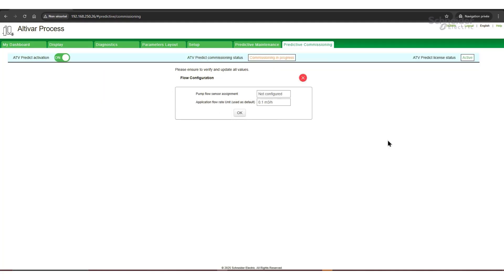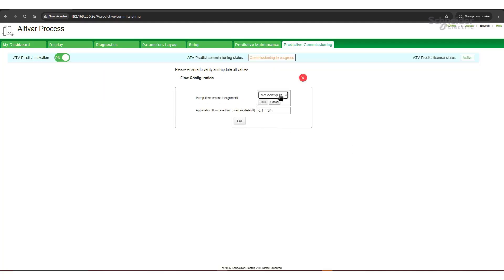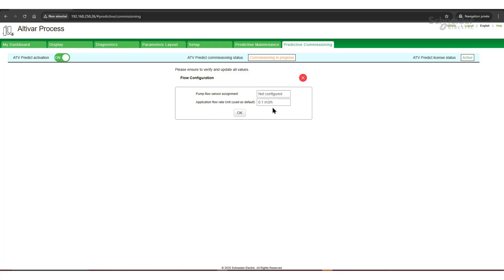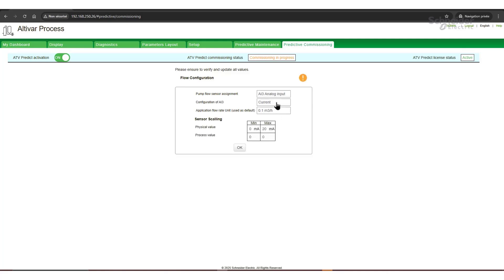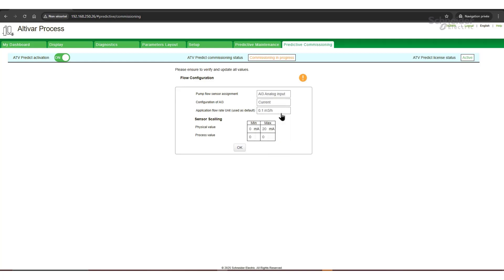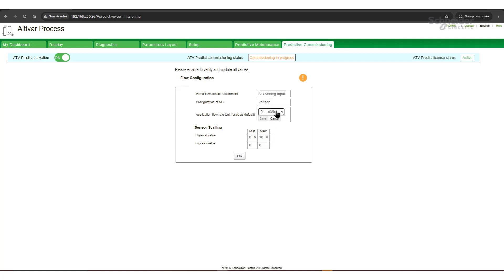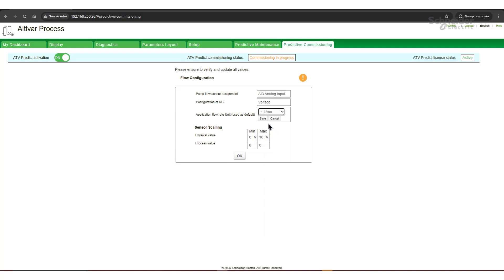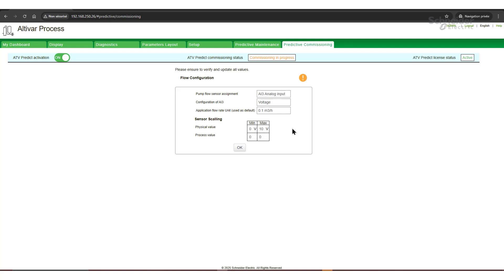Next step, click on flow sensor. Our flow is connected to AI3. It has a voltage type analog signal. We change the units to liters per minute according to our application. Now we can scale the signal so that the physical value will correspond to the process value.